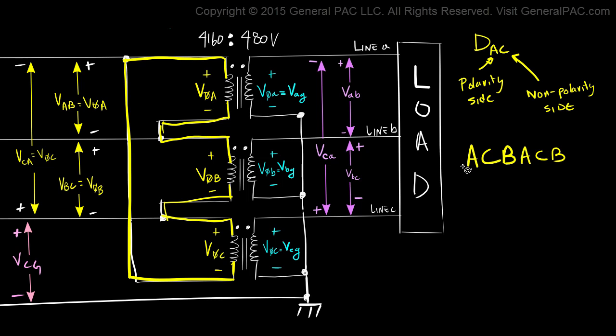So the first pattern is this right here. The polarity side of winding A is connected to the non polarity side of winding C. This is the second pattern and what we are saying is that the polarity side of winding B is connected to the non polarity side of winding A.